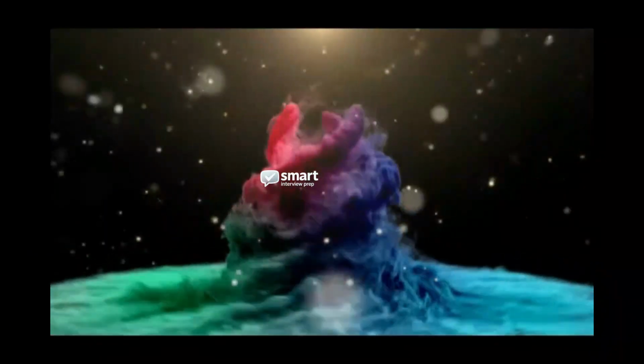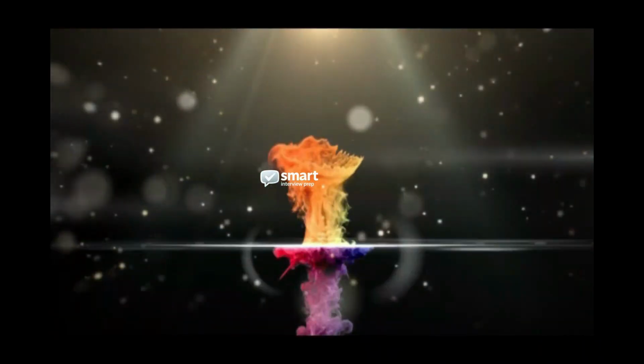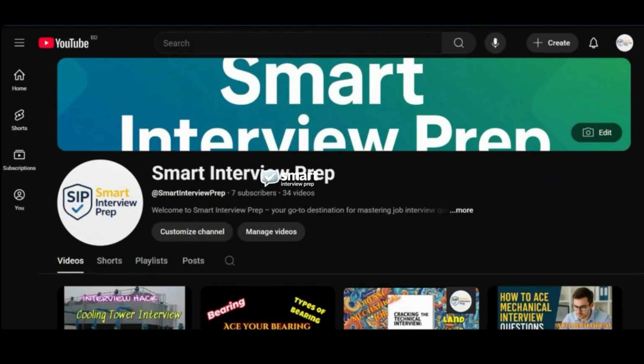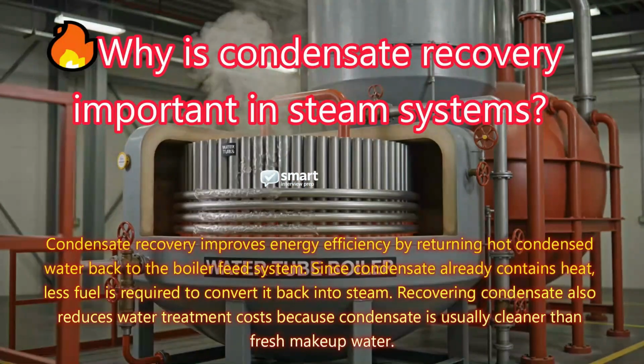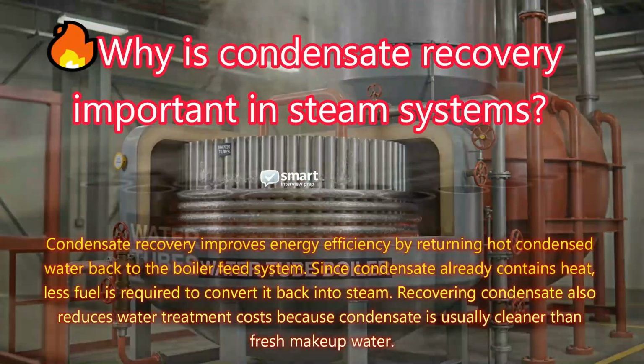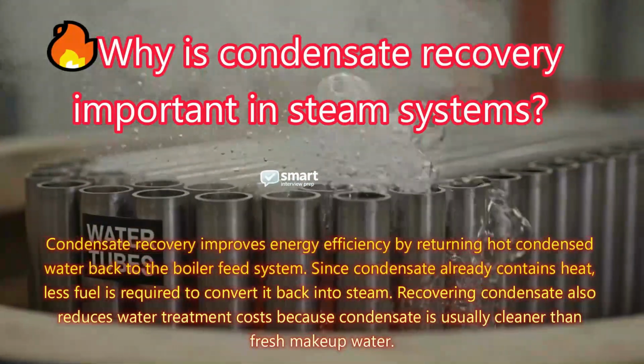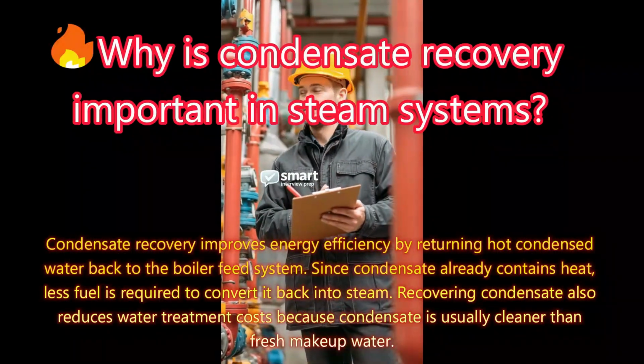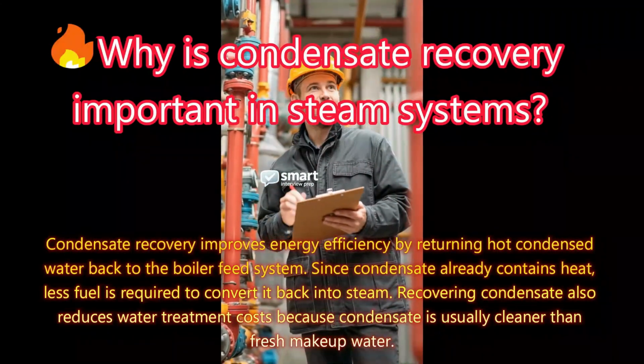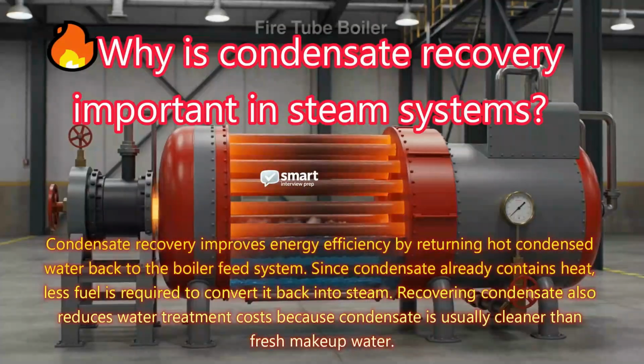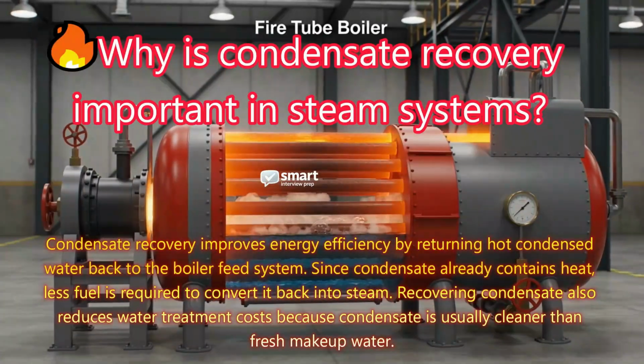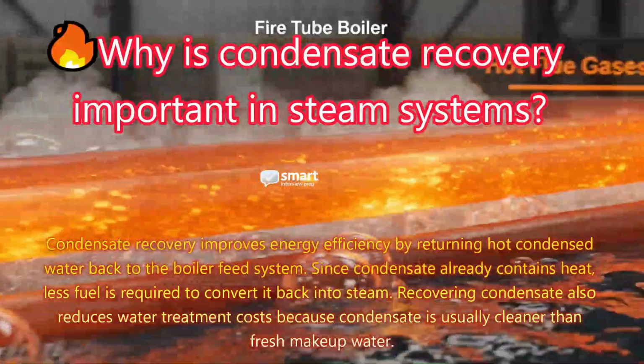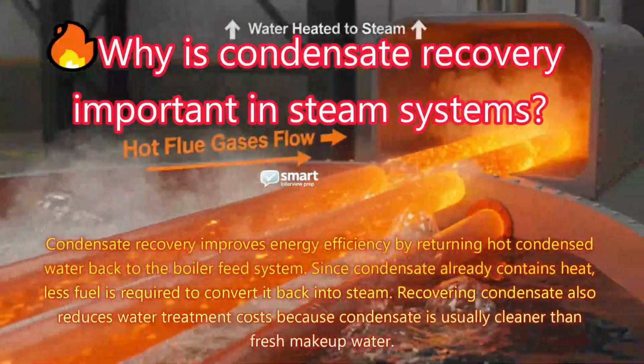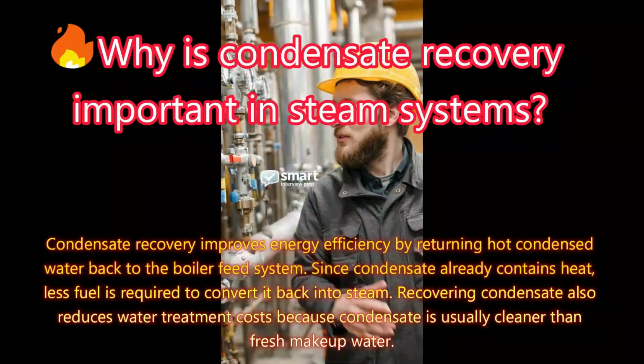Why is condensate recovery important in steam systems? Answer. Condensate recovery improves energy efficiency by returning hot condensed water back to the boiler feed system. Since condensate already contains heat, less fuel is required to convert it back into steam. Recovering condensate also reduces water treatment costs because condensate is usually cleaner than fresh makeup water.